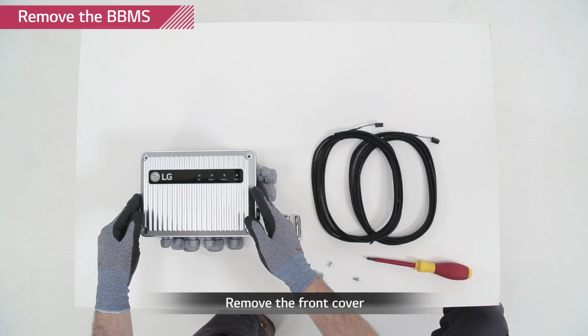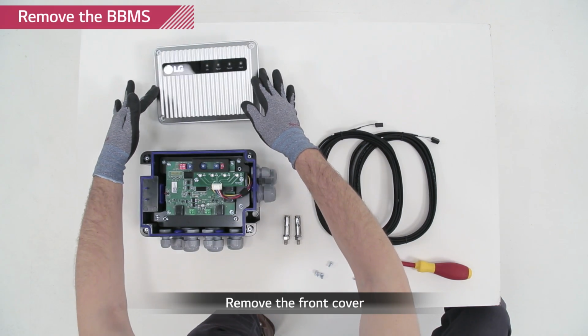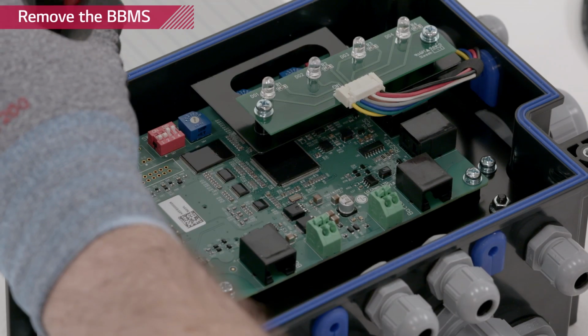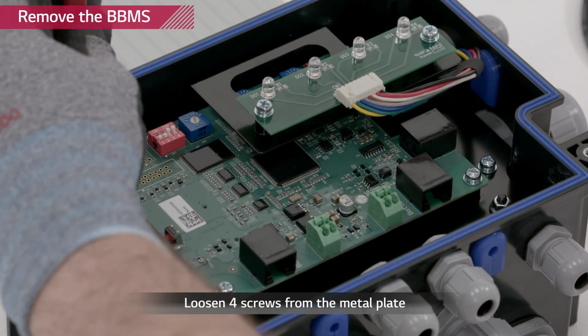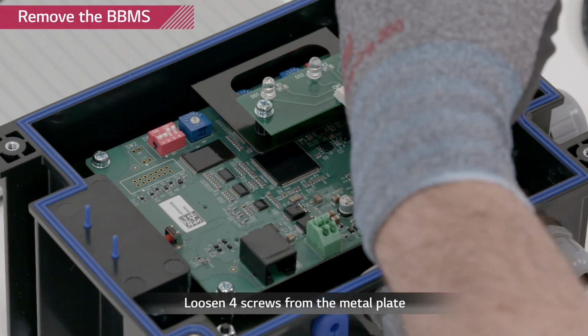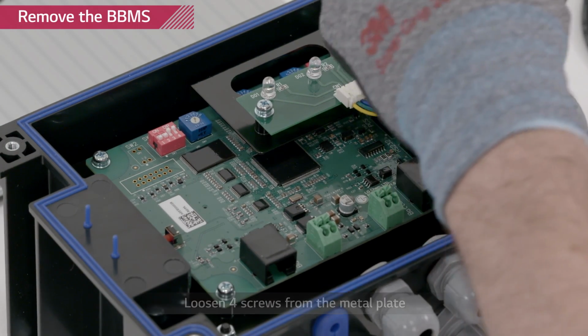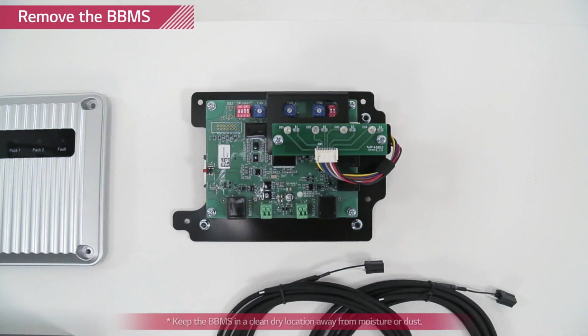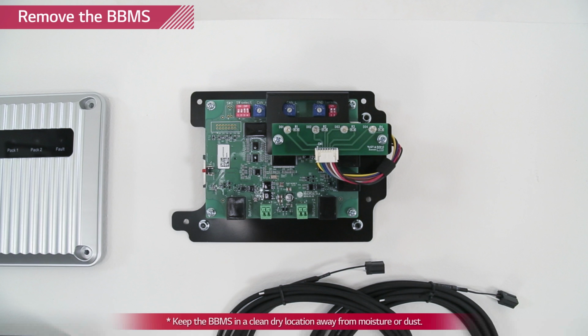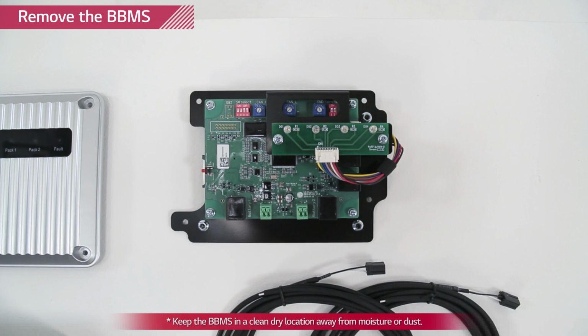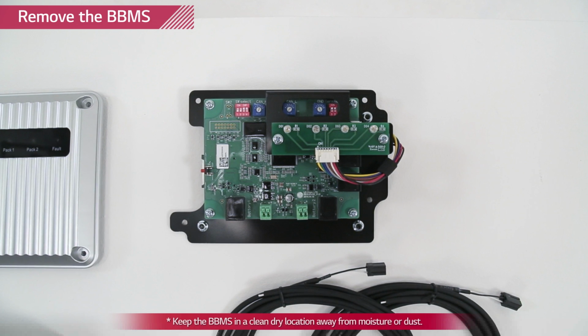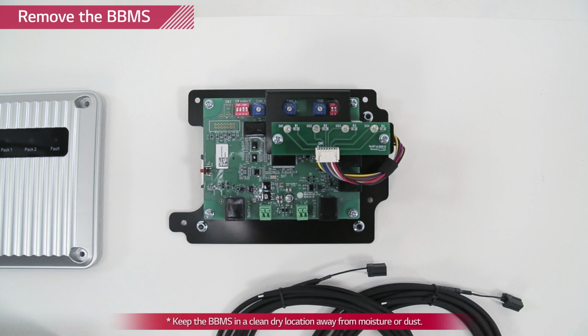Remove the top cover of RESU Plus by loosening the 4 screws at each corner of the product. Remove the bank BMS inside by loosening 4 screws at each corner of black metal plate. The bank BMS is a PCB and contains sensitive electronic components, which need to be taken care of with caution. Make sure to place the bank BMS in a safe location while mounting the RESU Plus to the wall.